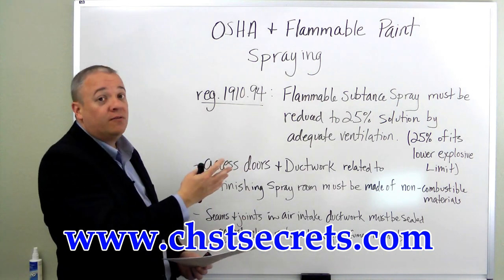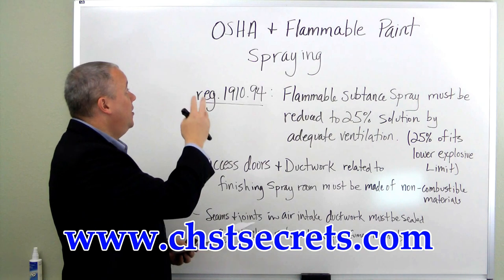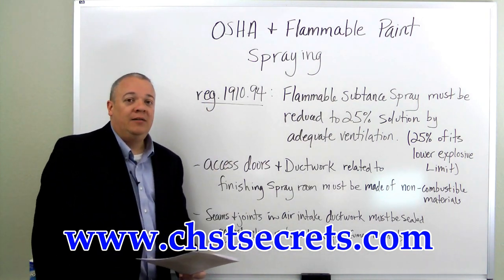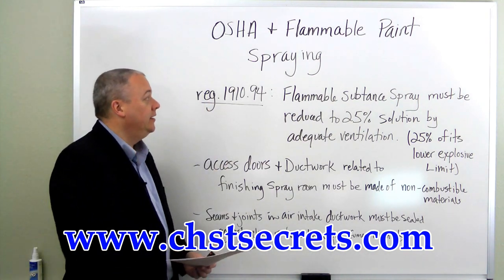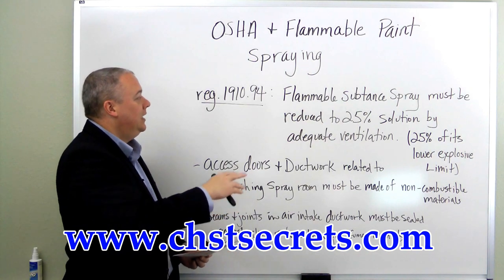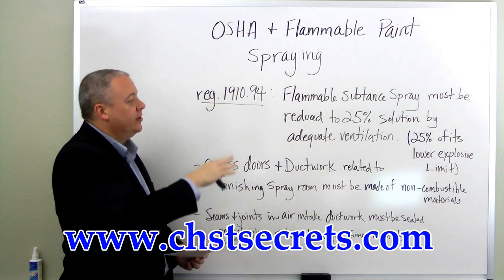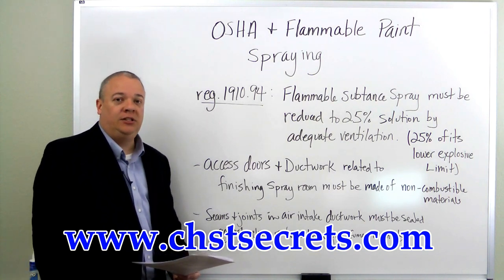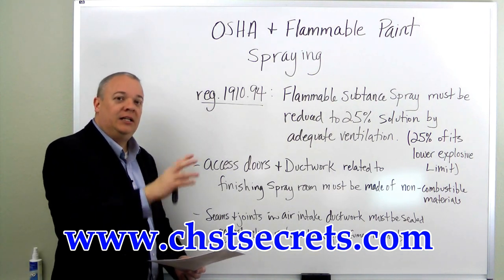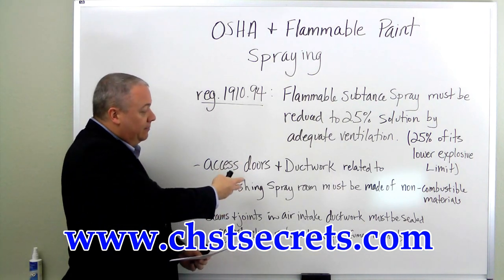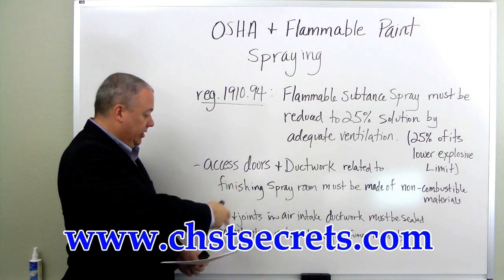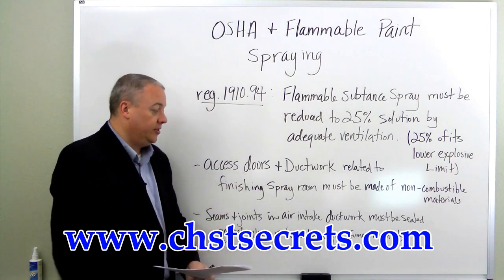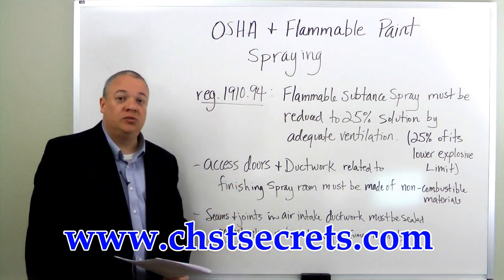This is a basic overview of OSHA regulation 1910.94 and subsections related to flammable paint and flammable substance spray. Safety requires that it be reduced to 25% of the lower explosive limit through adequate ventilation, that the ventilation and doors leading into the room be made of non-combustible materials, and that they be sealed against release of hazardous vapors, fumes, or mists.